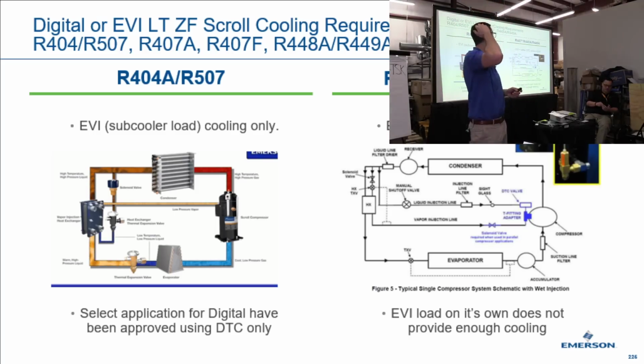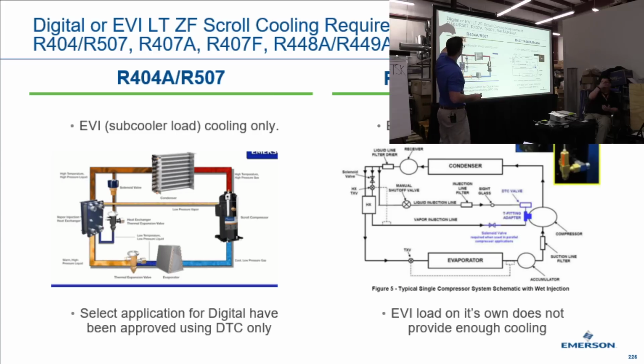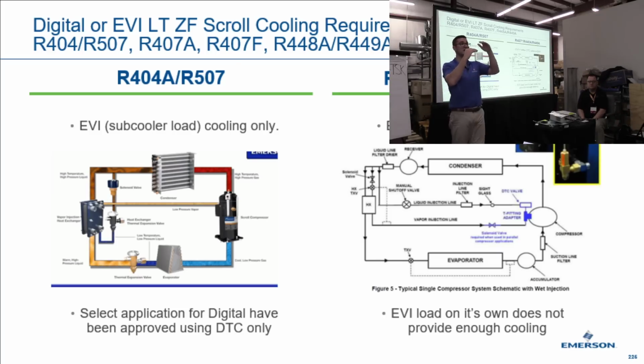So it's for efficiency. So the EVI, as you can see here, with 404, 507, EVI subcooler load cooling only. So this brings the efficiency up of your system. So we talked about compression ratio earlier, right? So what we're doing here on this compressor is we're taking gas, and if we're running just say 20 psi and 200 psi for an example, I'll just throw you that example out. On the side, this tube right here, we're pushing in 55 psi. So what does that do now to my compression ratio? It closes, right? So now I don't have such a big compression ratio, so there's efficiency gains there.